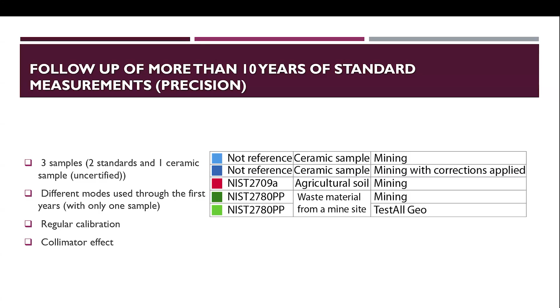First, while no certified sample was available at the beginning of 2013, some systematic errors were noticed in the measurements, especially for the light elements. And so a first factory calibration was applied in 2014. And since then, precision tests were regularly performed, at least twice per year, to verify the precision of the results, and systematic factory calibration was applied to the device to verify the stability of the acquired measurement, at least in the precision of the data acquisition. In 2019, for this equipment, the X-ray tube was changed due to its failure, and from 2019 till 2024, no factory calibration was applied, and the last factory calibration applied was in mid-2024.